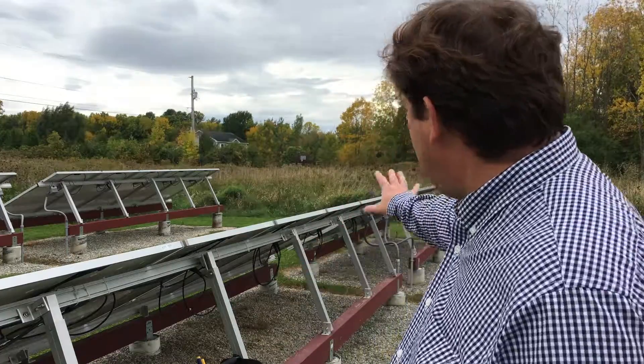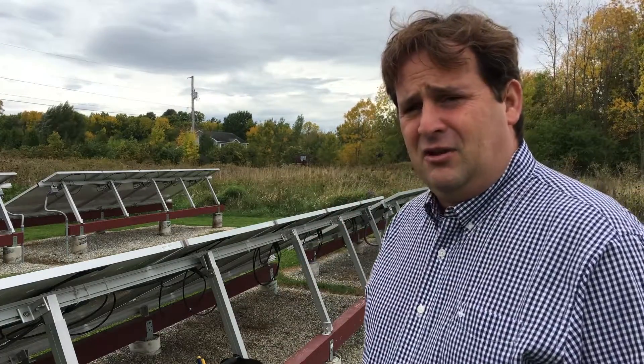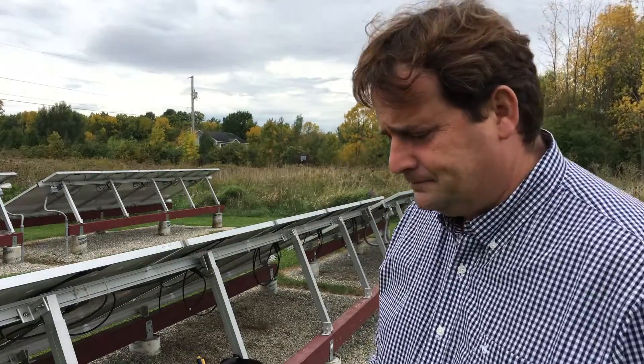I'm thinking that because the M250s are placed at the very end of the trunk, they're not performing as well as the M215s, which are at the beginning of the trunk where it interfaces with the junction box and disconnect. I want to thank Jason Andrade from West Coast Sustainables in California.